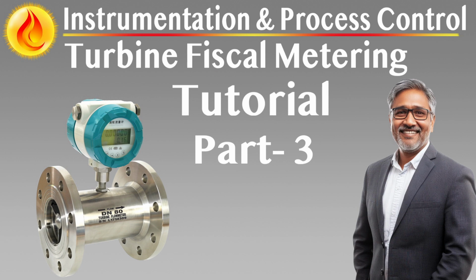Transmitters must be mounted with 3-valve manifolds that include an additional impulse line connection. This allows connection to a deadweight tester for calibration checks without removing the transmitter from service. When specified, a certified deadweight tester must be provided with uncertainty better than half the accuracy of the transmitter under test. To support proving and calibration operations, transmitters must be installed at points that represent the true process pressure with minimal lag or dampening. Bourdon tube-type pressure gauges must be installed locally on each stream with a minimum dial size of 100 millimeters for clear visibility.